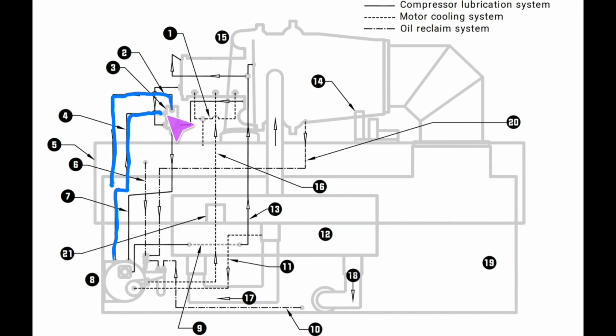And then once it comes in the side, it's allowed to then just vent back to the evaporator through a pipe. So it's just piped back into the evaporator, and the low pressure side of the evaporator allows it to pull back through. So just something to be aware of is that's how the additional vapors that collect here get vented. Next, we will discuss the oil management side of it.